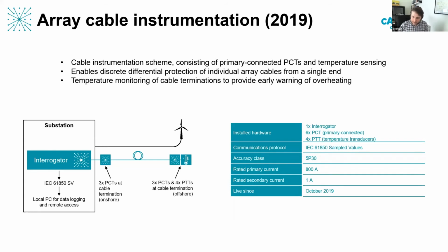But basically, what we've done is we've instrumented the cable with current measurements at both ends, and also inside the turbine, we've deployed temperature monitoring on the cable terminations. Because we know that that's a very problematic aspect, which I think is the most significant cause of failures. Correct me if I'm wrong, Tom, but that's something that quite often goes wrong. But yeah, sorry, carry on.